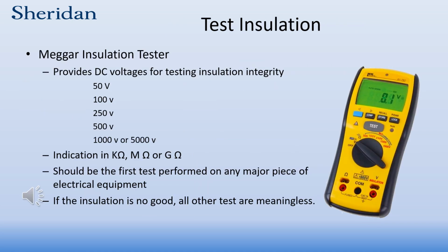The first test we'll talk about is the Megger insulation test. What it does is provide a high voltage to the conductors, testing to see if the insulation breaks down under stress. It comes in various voltage levels: 50, 100, 250, 500, or 1,000, and some can go as high as 5,000. The reading is in ohms, but instead of just ohms, it's kiloohms, megohms, or gigohms, because the value should be very, very high. You should have very high resistance values between any conductor and ground or the chassis.